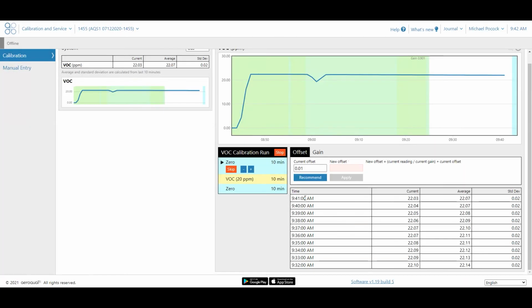Okay, so we have completed our zero calibration, so we want to skip that section. It's very important that this arrow, when you're doing the span calibration, is on the VOCs, and it's really important that this number here is the same as the concentration in your cylinder. So I've got 20 ppm in my cylinder. You're going to have 20 ppm here. If you had 1 ppm in your cylinder, you've got to have 1 here, because that's the way that the software will know how to adjust your calibration.